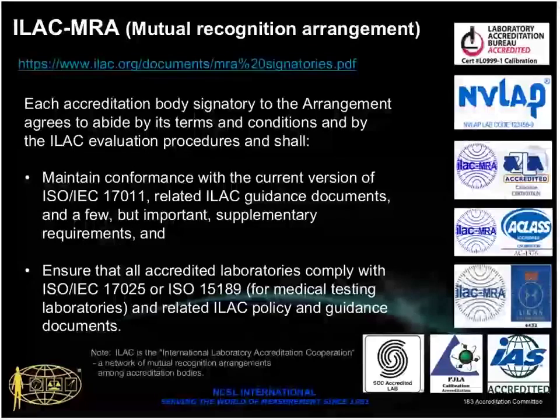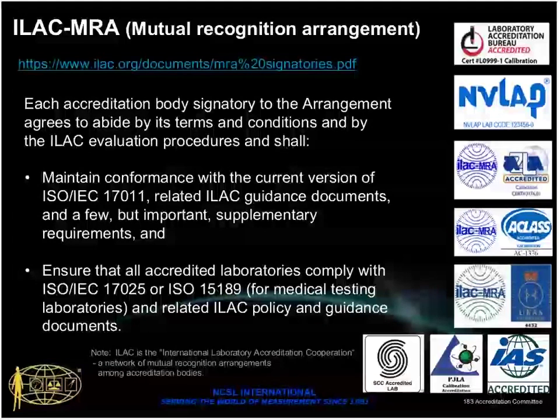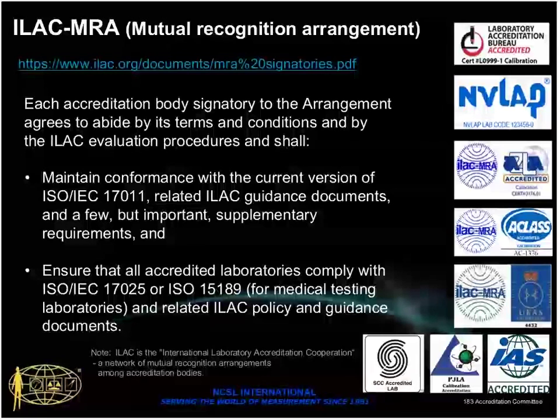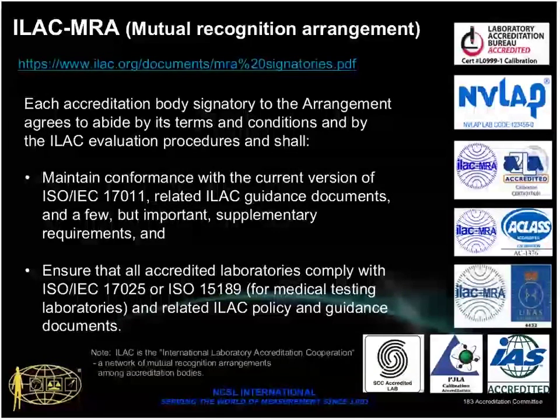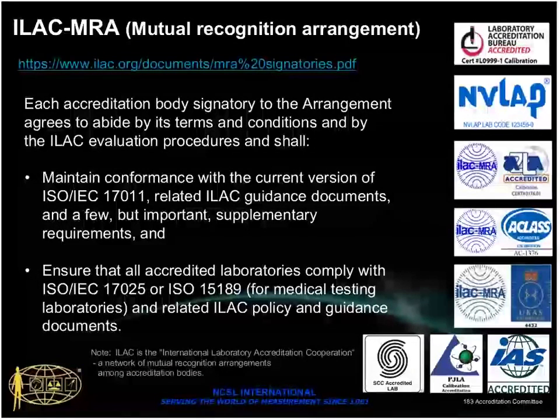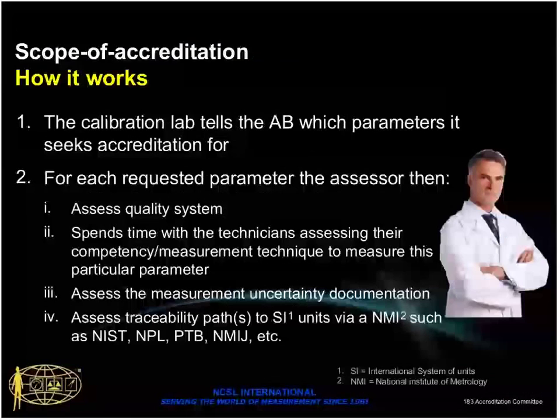If you go to one of those laboratories and you don't ask for an accredited certificate, you are on your own as far as the accreditation body underwriting the credibility of the procedures and of the budgets, etc. But most of the reputable laboratories, and indeed most of the manufacturers and the larger people, will use the same management system throughout their operation. But I would always suggest that you ask for an accredited 17025 calibration, but you are free to ask for a variant, which might be less in some ways and wouldn't bear the accreditation mark. But if you go to an accredited laboratory, you can be sure that the competence is there in the organization.